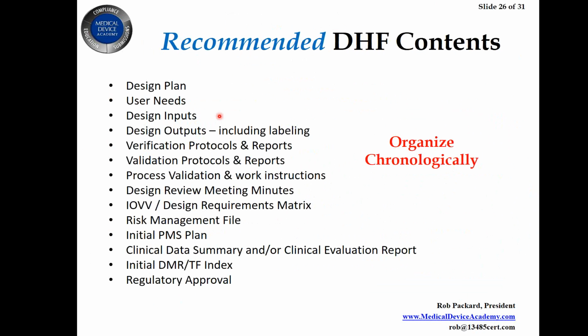Your risk management file, you may include each of those documents that were the risk management activities that I identified in the risk management plan, or you might just have a summary report that references all of those. So a risk management report typically will be a STED, or summary technical document, and that will identify each of the risk management activities that were done and the document that was produced for them. And then you'll have a hyperlink in a virtual system to that actual document that might be controlled in your electronic archives.